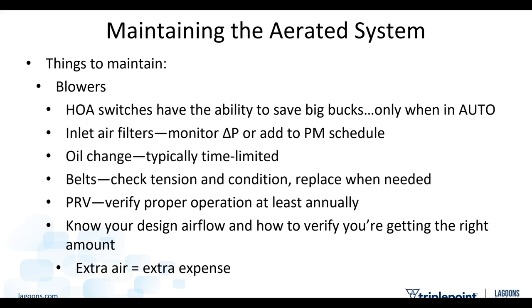They're costing you more money to run your blowers, and you're running your blowers harder. You're adding wear and tear to the machinery that you don't need to. Keep an eye on those inlet air filters, please. Oil changes very typically are based on operating hours, runtime, et cetera. And just look in the owner's manual. Make sure you look for anything that talks about extreme duty or a challenging site or locally corrosive environment or anything like that that might have a different schedule, and follow the manufacturer's recommendations for oil changes.